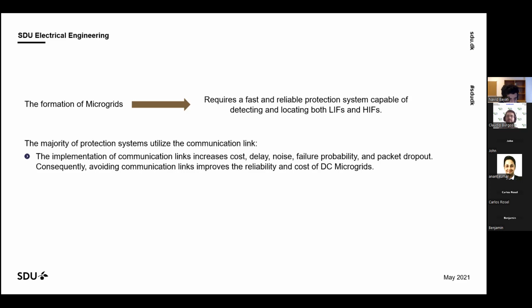But in the protection, if we are working on the microgrid side, because the microgrid is more at the converter level, we have a lot of renewables, and all renewables are connected to the main buses by converters. So when we have these kinds of systems, for sure we don't have any inertia. And when we don't have any inertia, the rate of change of the frequency, the rate of change of the voltage, and the rate of change of the current during a fault, short circuit or any kind of disturbance is high. So if we have a fault in the microgrid, the fault current goes very fast to the peak point.